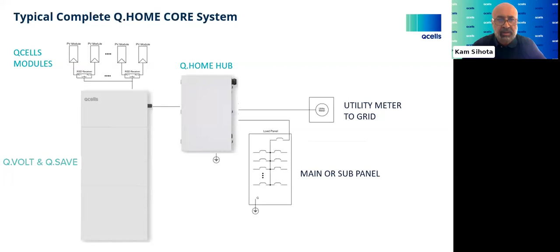Next we'll look at two different applications. We talked a bit about DC coupled, meaning your PV modules tie into the inverter and battery - it's a complete system. On the right-hand side, the lower portion is an existing PV site, and this diagram shows microinverters - PV modules on the bottom with microinverters and a combiner. That's the existing PV site that might be on a rooftop somewhere. You could walk in and sell our battery inverter system and have it AC coupled - in other words, the common point of coupling is an AC connection. The battery, which is DC, has an inverter portion that generates AC and brings it into the hub, and the hub ties in the existing PV, depending on the application.